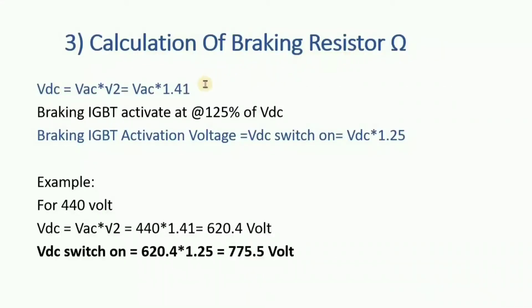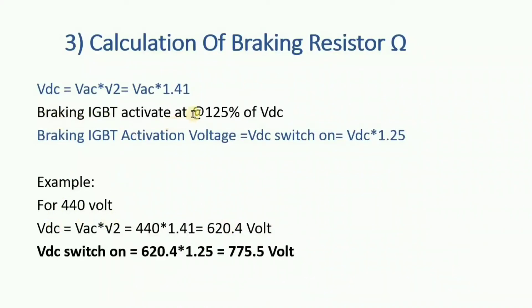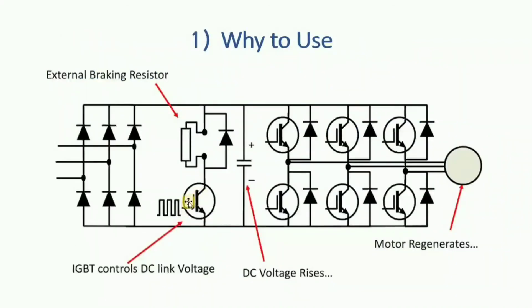Now let's calculate the ohms of the braking resistor. First we calculate the VDC of the drive using the formula: VDC = VAC × √2. The braking IGBT activation level is at 125% of VDC. For example, with a 440V AC input: VDC = 440 × 1.41 = 620.4V. The switch-on level is 125%, so 620.4 × 1.25 = 775V. This is the voltage at which the IGBT gets triggered for braking.